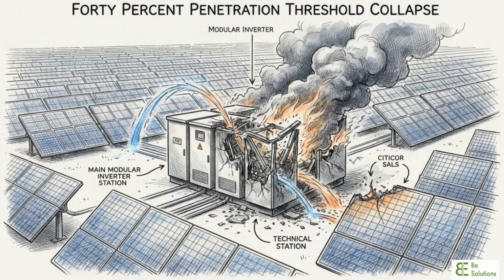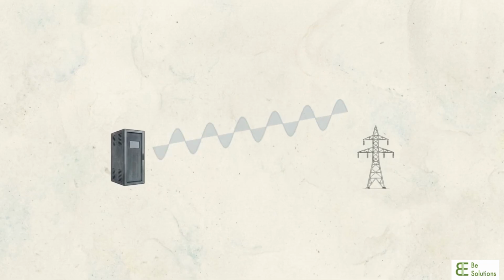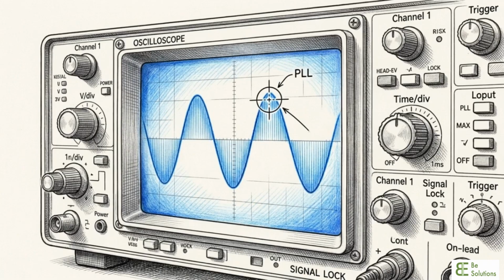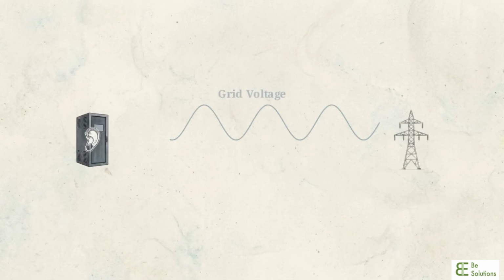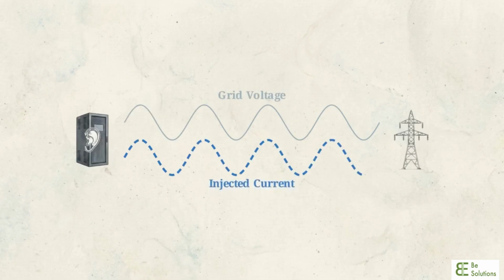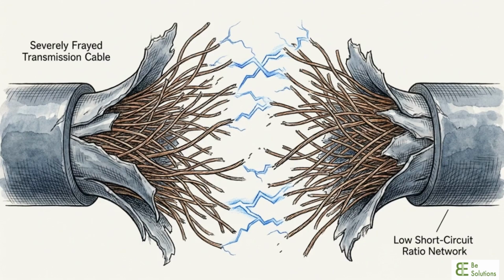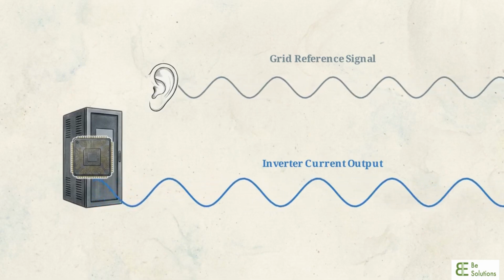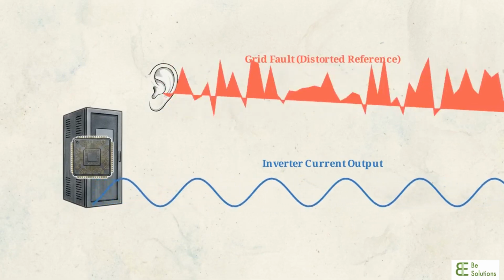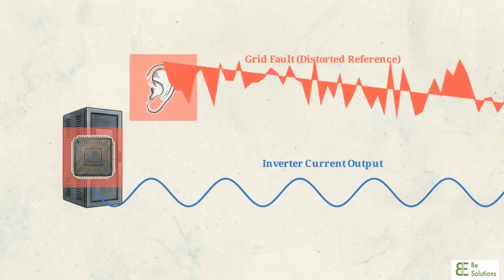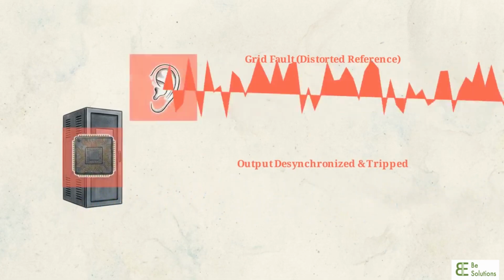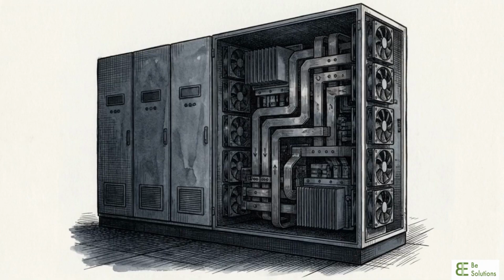Currently, the vast majority of installed systems use grid-following inverters. These function strictly as controlled current sources. They require a phase-locked loop to measure an existing external voltage waveform. The inverter essentially listens to the grid and then injects a matching current to synchronize with it. The flaw in this design appears in weak networks with low short-circuit ratios. When a fault occurs, the external voltage reference wavers. Without a strong signal to follow, the grid-following inverter's control loop becomes highly unstable, often causing the unit to trip offline exactly when the grid needs support the most.